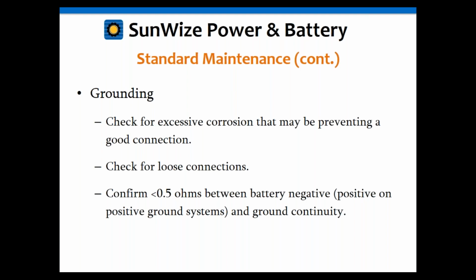But it's important to have a good ground because that really helps with transients. If you get some type of surge, a voltage transient, and you don't have a good ground, that could damage your equipment. So this is a good preventative thing with regards to maintenance, where if you're checking that, making sure that ground is good, giving a path to ground for any surges you might get from transients, voltage transients that can occur from a nearby lightning strike.